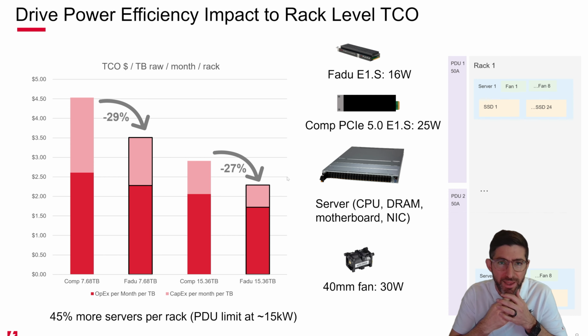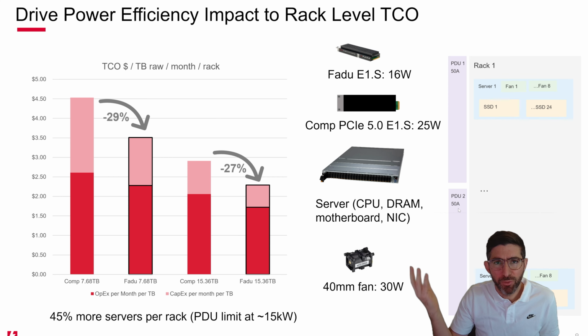Now, when we take that same concept and look at how it makes a difference at the rack level, we can decide on a standard rack, and we just said a 15 kilowatt rack, which, if you do the math, at 250 at the PDU running 3-phase, is something like 16 kilowatts. But we'll just say this is close. We just asked, what is the max number of servers you can fit at the power levels that we just described on the last slide? How many of those servers can you fit in 15 kilowatts? And if you're running at that lower power, you can actually fit 45% more servers and still stay in that 15 kilowatt envelope.